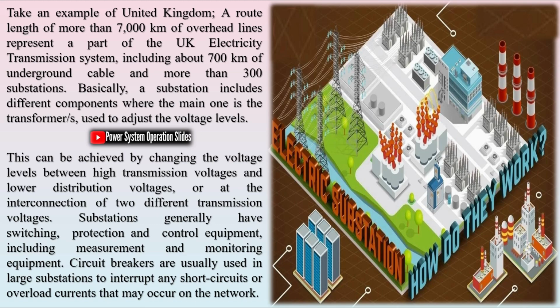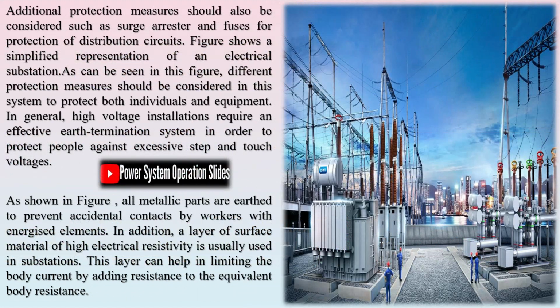In order to fulfill the safety limits and requirements, every element within the electricity system, such as pylons, overhead lines, substations etc., should be designed in accordance with the relevant national and international standards. The electrical energy, from generation to consumption, passes by multiple adaptations where different levels of voltages may be required. Step up and down of the voltage level is set up through the electrical substations.